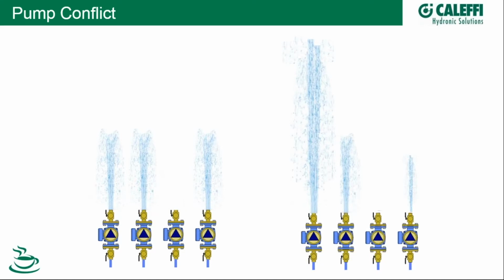What we don't want to have happen is pumps being affected by the action of another pump. When you turn off a pump in this, you typically have all the other pumps increase in flow rate to some degree, even excessively. That's one of the problems with coupled pumps: your flow rate can exceed, excessively, the design flow rate for that circuit. And obviously there are potential issues with that, including erosion and corrosion inside the pipe, so leakage as a result of the walls wearing thin and eventually leaking.